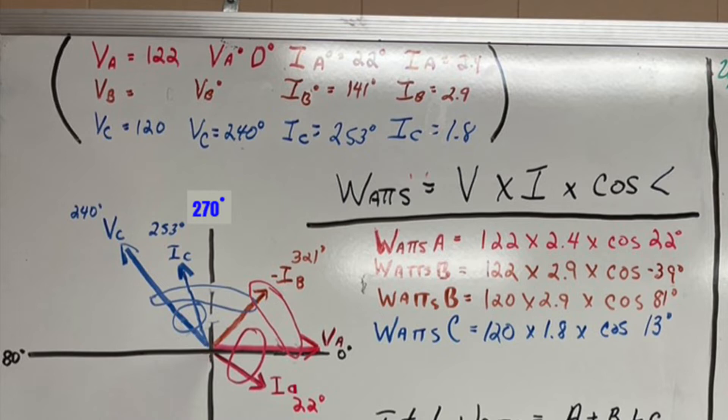Now phase B, what we have to do, remember it's this current passes both potential coils and it's flipped 180 degrees reverse polarity. So we're going to go ahead and circle VA all the way to negative IB. And so what are the calculations to be? I'm going to use the voltage A which is 122 volts times the current B which is 2.9 amps times the cosine of negative 39 degrees. 360 minus 321 degrees gives you 39 degrees.